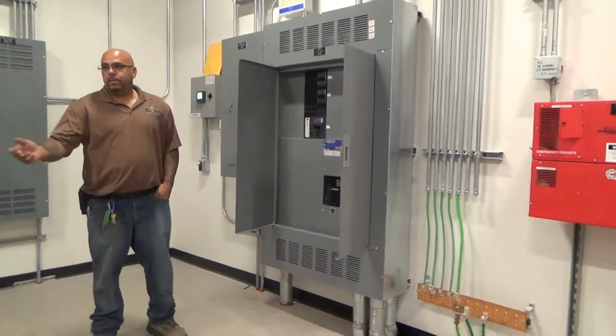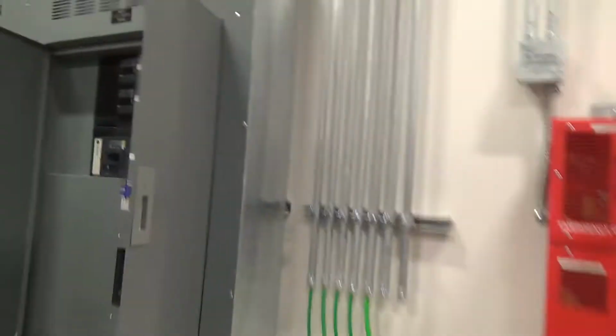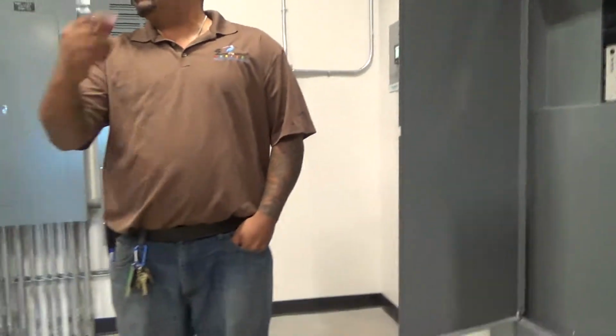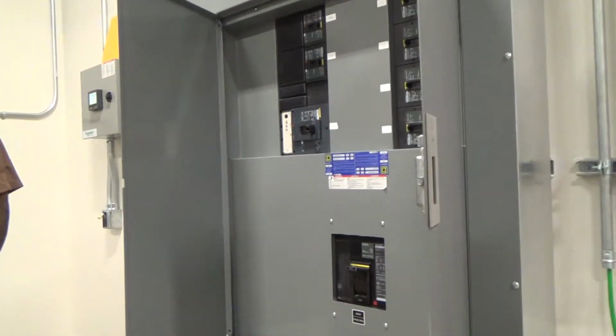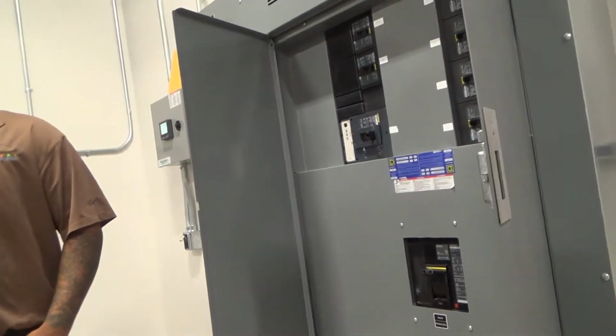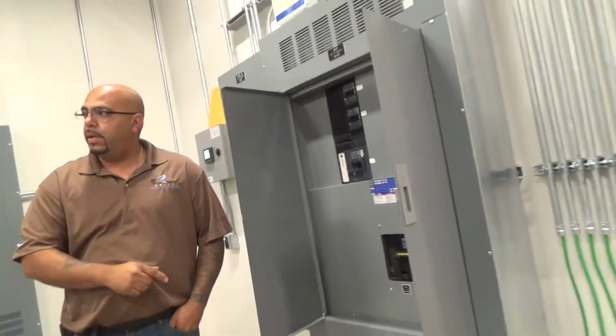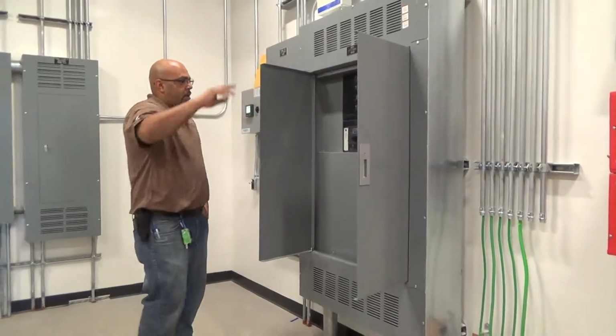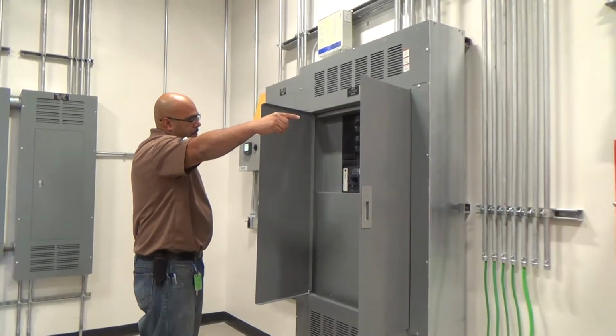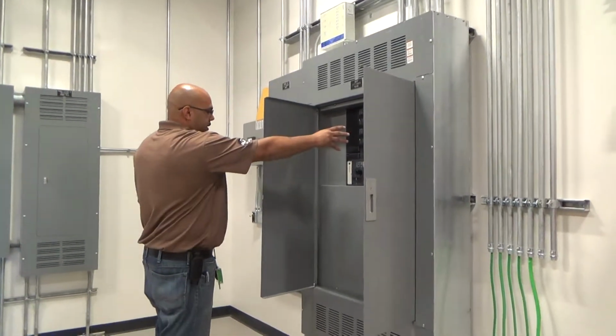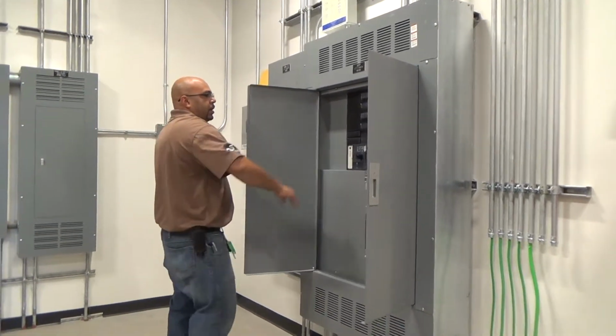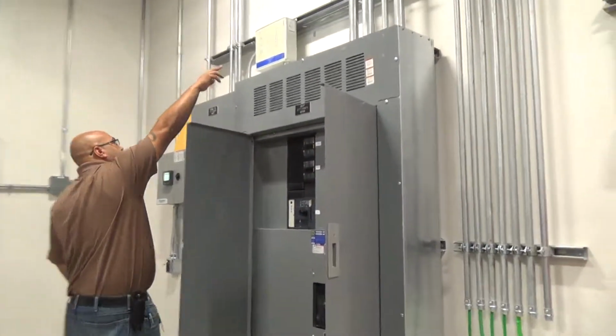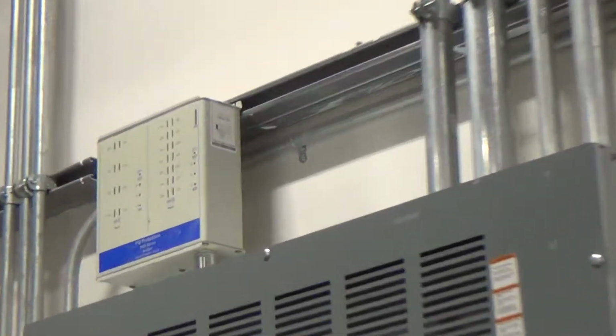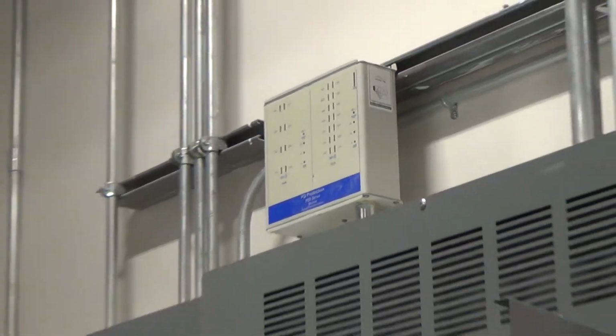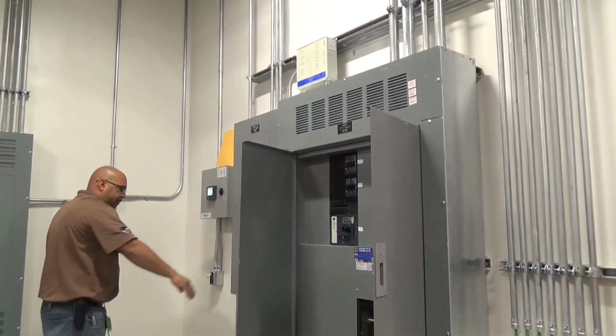As we walk downstairs to the first floor electrical room, I'll show you exactly where the main disconnect is for the entire building. We have an 800 amp service coming into this building. From that 800 amp main disconnect, it feeds into this MDP panel. The MDP has its own surge protector. And then we distribute along to the high voltage panel on the second floor.